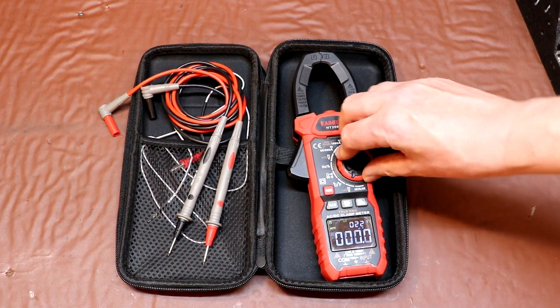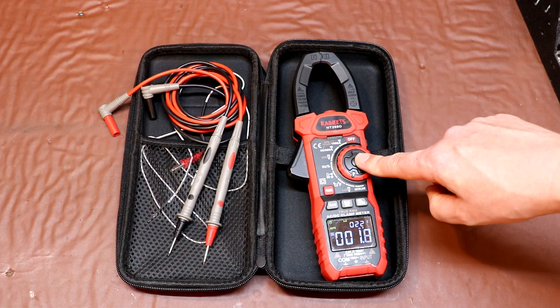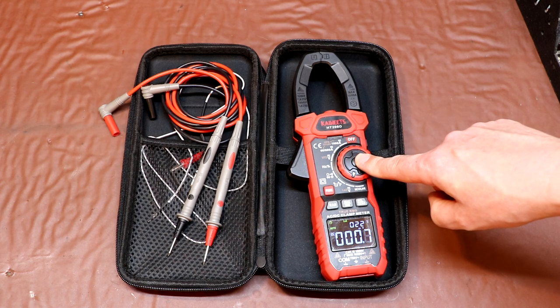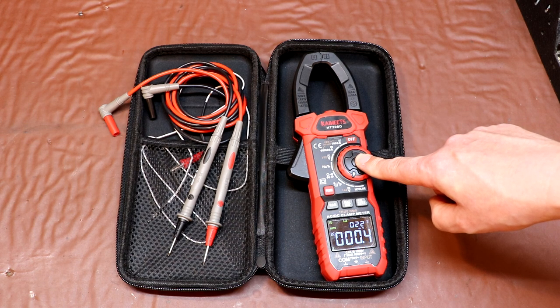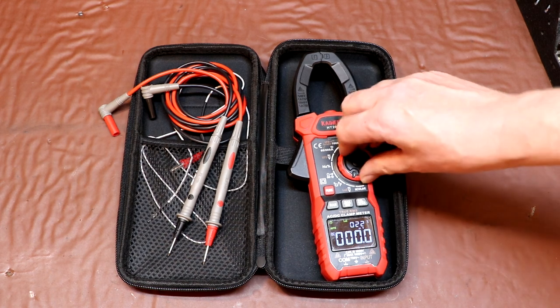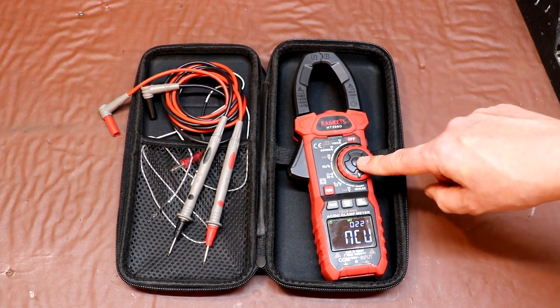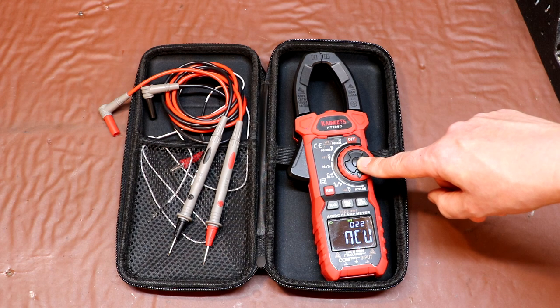Moving on to the low Z voltage range, I can really see that that would be really useful for determining whether or not you were seeing ghost or phantom voltages. Moving on to the non-contact voltage detection, that really did work very well and had an excellent range.